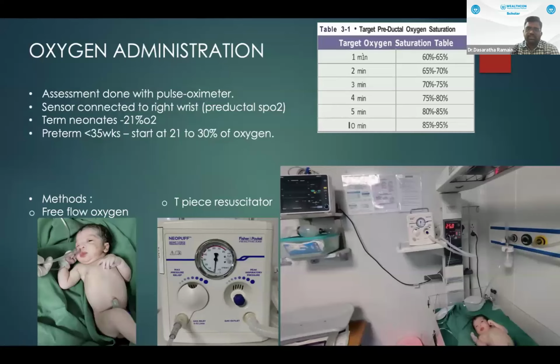Apart from this, in the equipment check, as Mahesh rightly demonstrated, we should always check for leaks by closing the gas outlet and the pop-off valve. Only then can we know whether it is a leak-proof self-inflating bag. One more important aspect is that while checking the laryngoscope, the bulb should be tight. Otherwise, accidents may happen while intubating. These things I wanted to bring to the notice of all fellows.